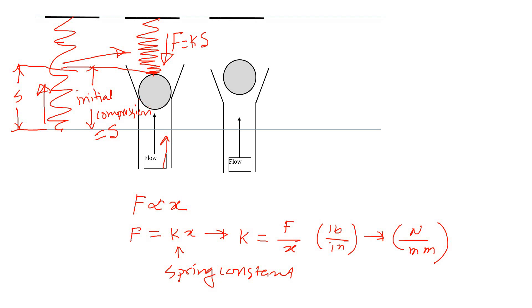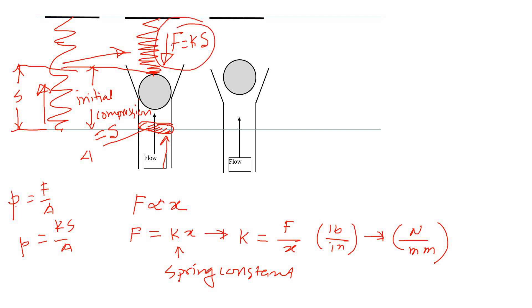If we know the cross-section area of the pipe blocked by the ball, let's call it A, we can calculate the pressure. Pressure equals force divided by area, or ks divided by A (P = ks/A). This pressure will just balance the spring force, which is why it's called cracking pressure.